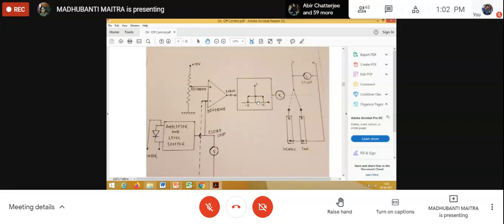How long will it decrease? Ideally, until the temperature reaches 68 degrees, that means 72 minus 2. At that point, or if it's slightly below that value, the error value E, R minus C, is less than or equal to E. Again, at this trigger point, the output of the Schmitt trigger will change. From this point to this point, the fan was connected in the circuit since the relay was de-energized as H1 is 0. Now at this point, when the temperature is 68 degrees, H1 will switch from 0 to 1, the fan will be disconnected from the circuit and the heater will be connected to the circuit.